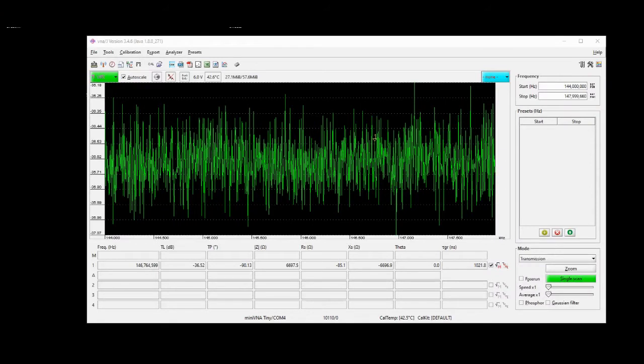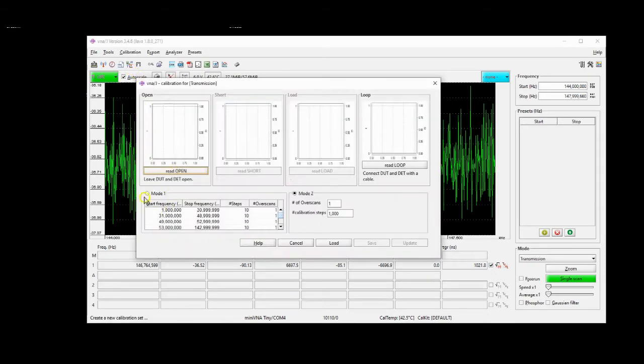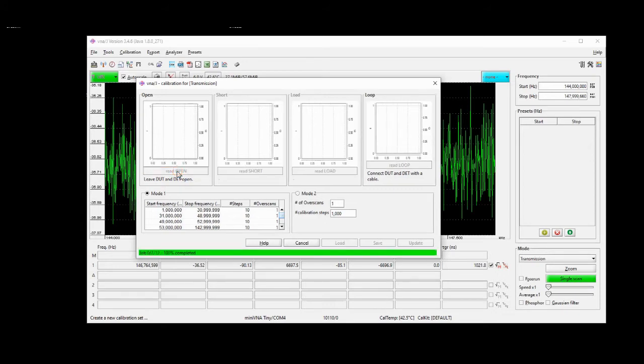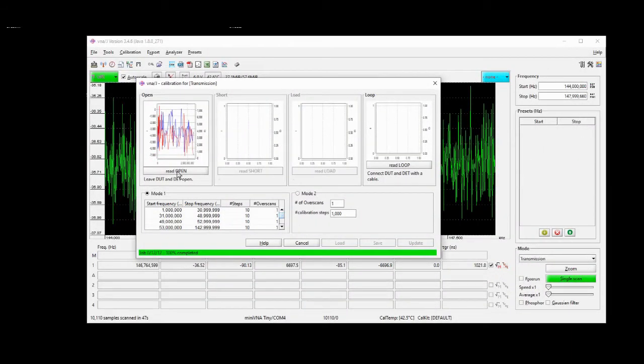We are now ready to calibrate in preparation for measuring the actual gain of the little preamplifier. So we're going to go through the same steps as before. Calibrate, create. We're going to choose mode 1. Now my cables are out on the table, separated from one another. We're just going to read open. They're not connected to one another. And we sit back and take a break. It's now done reading the open. Now we'll connect our cables together through our menagerie of adapters, and we read the loop. It is done reading the loop, and as before, we could save the data for future reference, but we're just going to update.